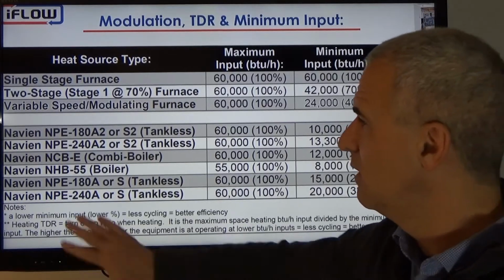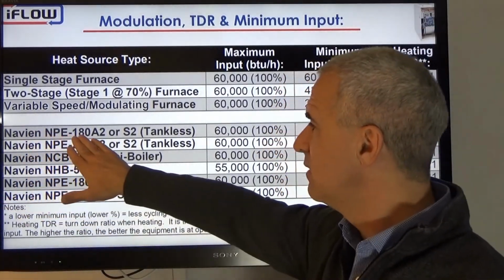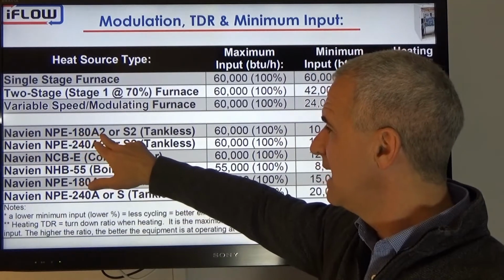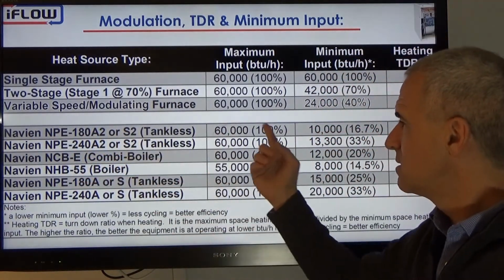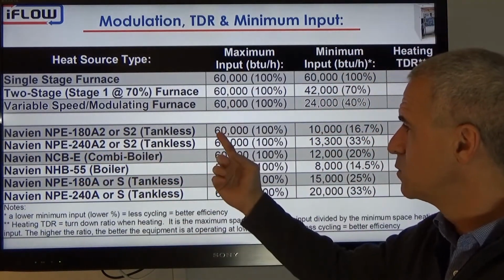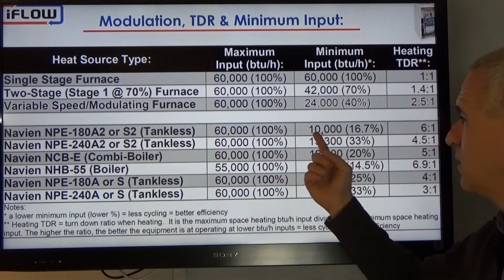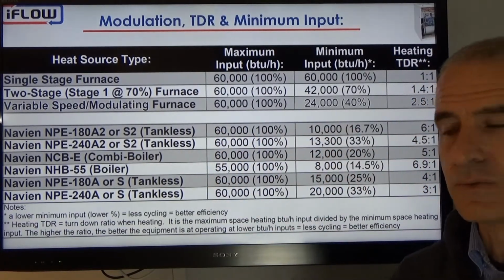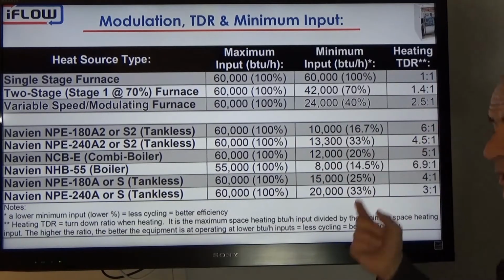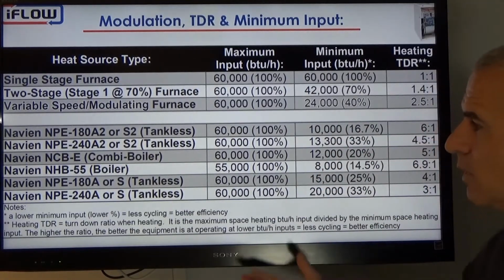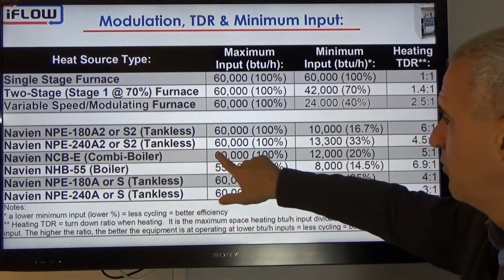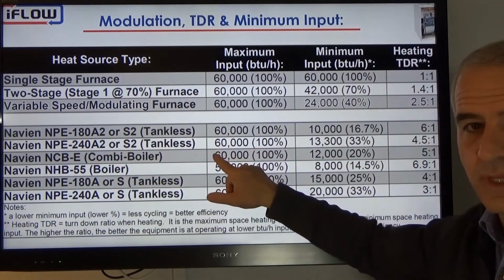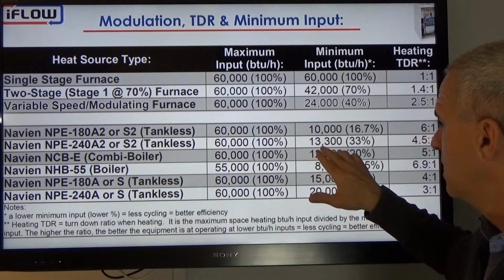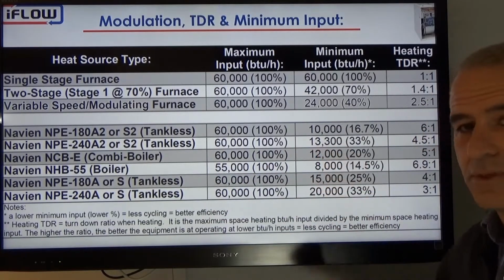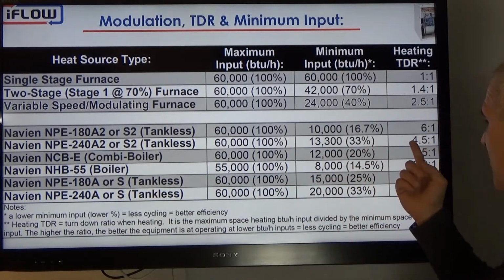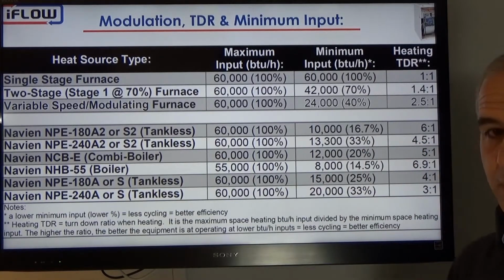Now let's look at the new Navien models. So now we have the 180A, the 180A2 or the S2. Let's assume we're going to do 60,000 BTUs worth of heating with that. The minimum input is 10,000 BTUs, giving us a 6 to 1 turn down ratio. What about the 240? Well, the 240, again, 60,000 BTUs on the heating side, not a problem at all. On the minimum side, we have 13,300, which gives us a 4.5 to 1 turn down ratio.